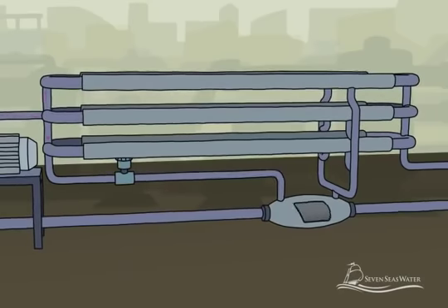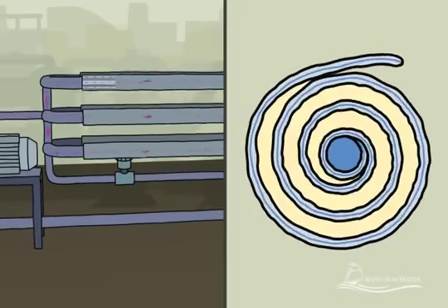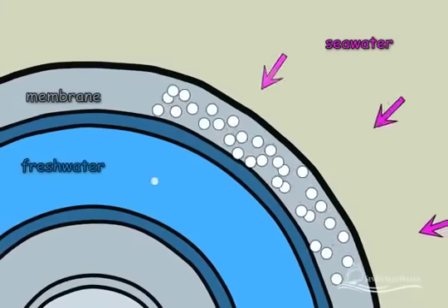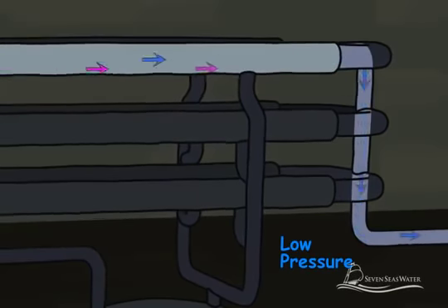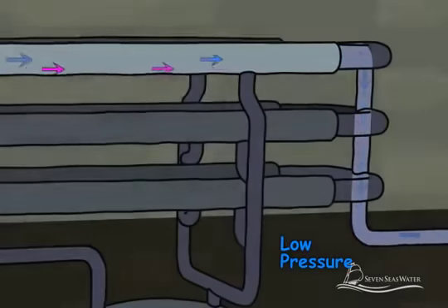As the pressurized seawater enters the pressure vessel and flows across the membrane surface, the water molecules are forced into and through the membrane envelopes, leaving the salt molecules behind. The desalted water passes through the membrane and emerges at low pressure where it is collected in a tube and directed to one end of the pressure vessel.